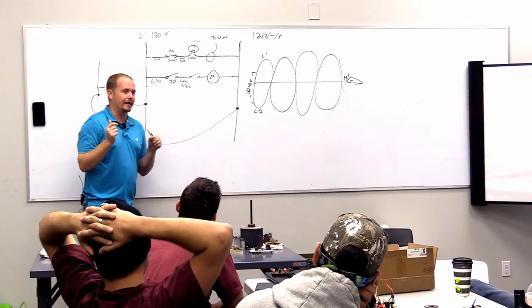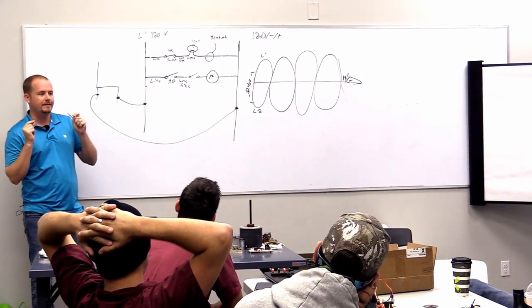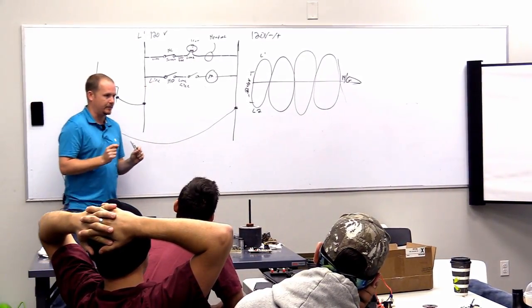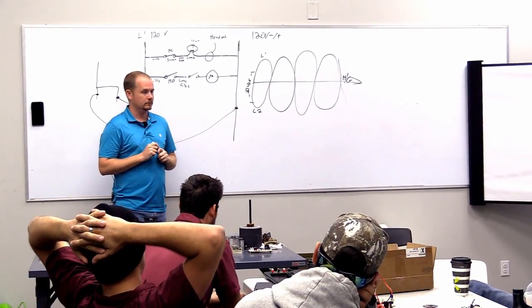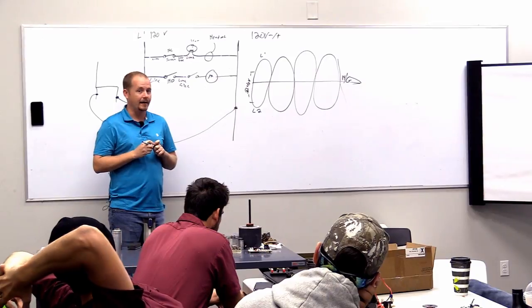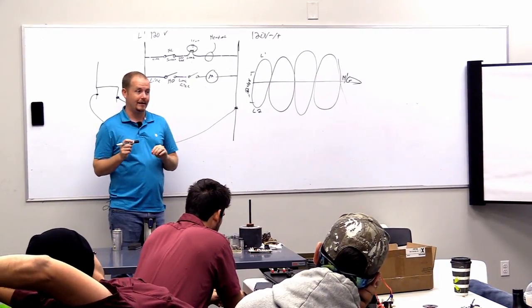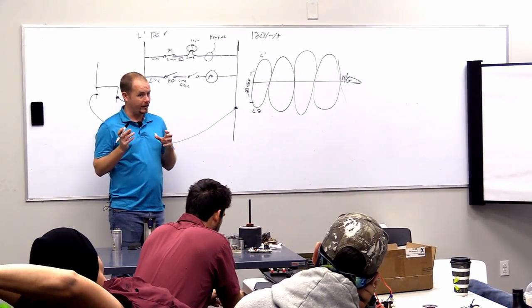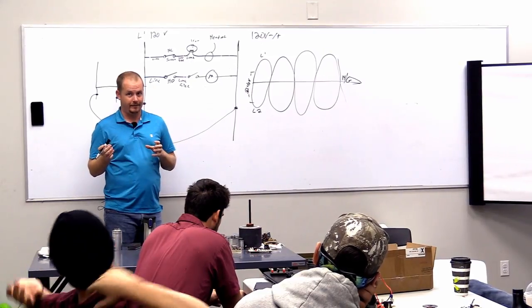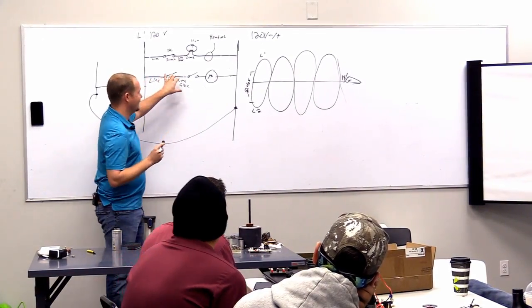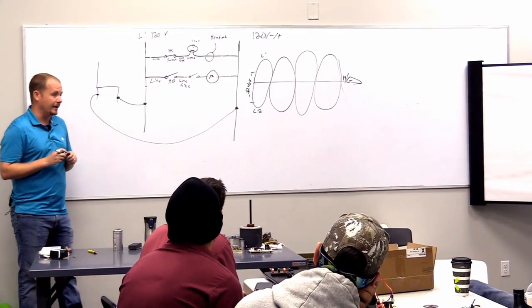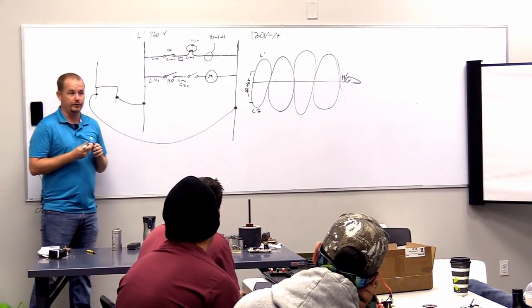Well, if you test to ground, but again, testing to ground is very fickle because you're relying on something when you test to ground. What are you relying on? You're relying on the fact that the ground is actually properly connected. And that's tricky, because it isn't always the case. Now, should it be? Yes. Is it a valid test? Yes. But it's not a valid test in this particular application. A better way to do it is to walk through the circuit.